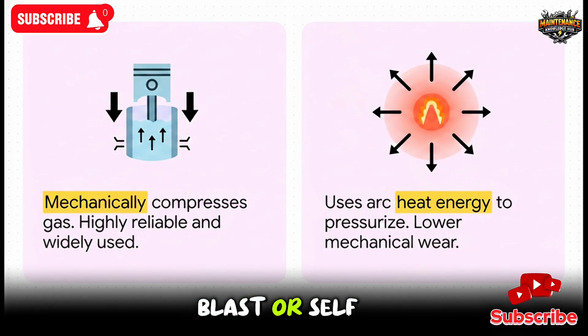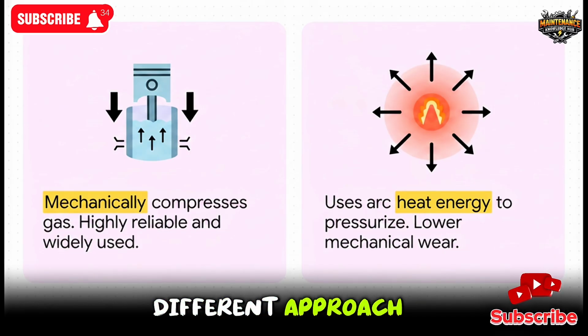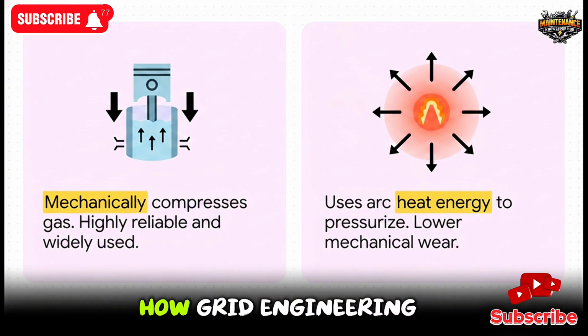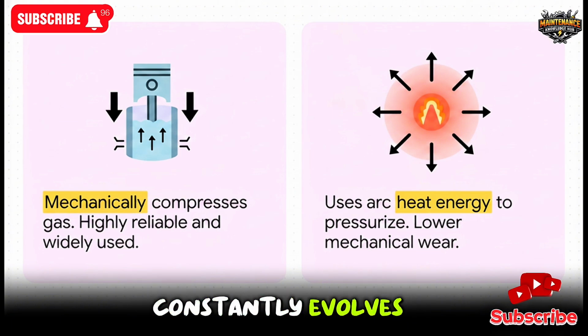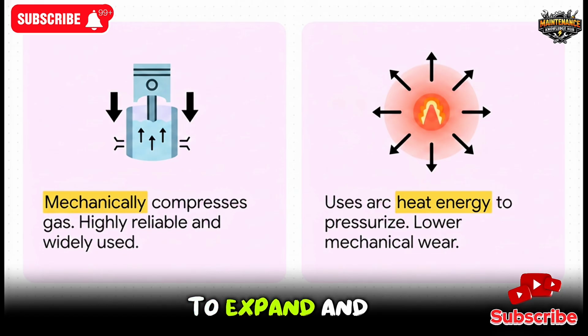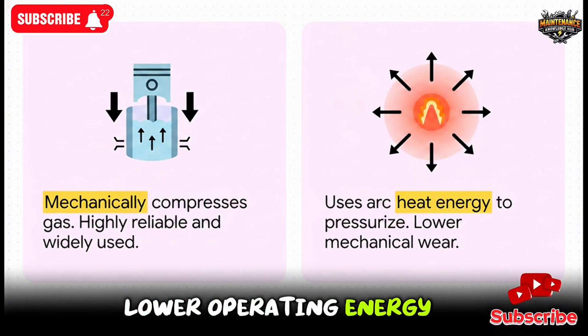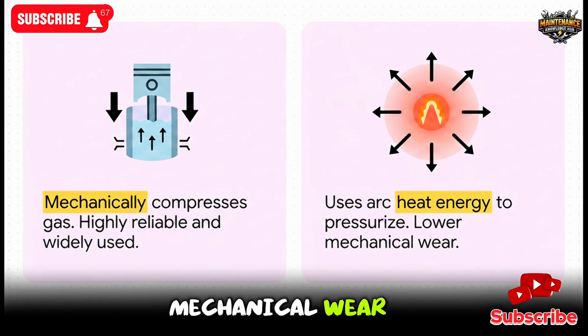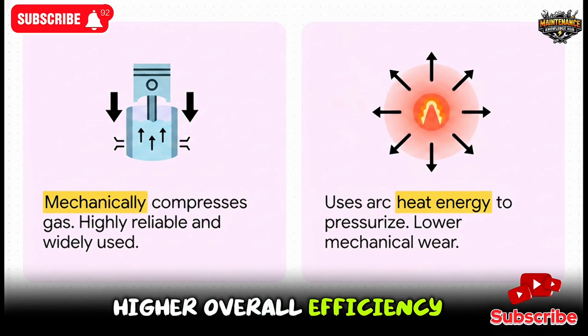But the self-blast or self-pressure type takes a totally different approach, and this brilliantly illustrates how grid engineering constantly evolves. It uses the massive heat energy generated by the arc itself to expand and pressurize the gas. By using the arc's own destructive energy against it to create that pressure, the self-blast type requires way lower operating energy, results in less mechanical wear, and just operates with a much higher overall efficiency.